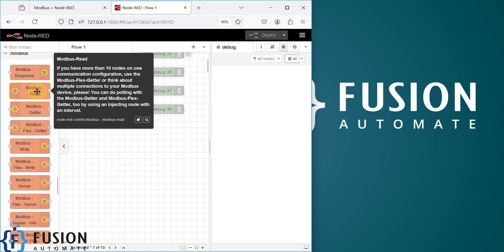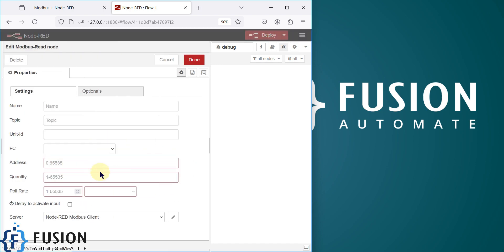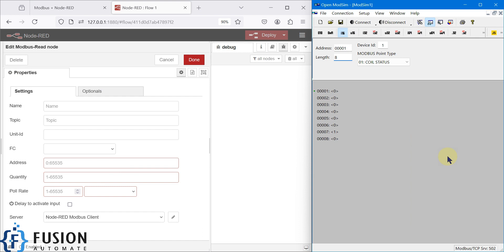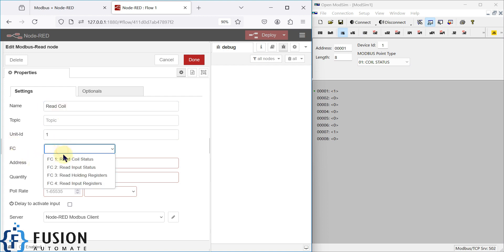I can drag and drop this Modbus Read node here and configure it to read the coil status. Here is our Modbus simulated device — a Modbus TCP device — so we have to provide its details in this Modbus Read node. The unit ID is one, and we are going to read the coil, so the function code is one because we are reading the coil status.